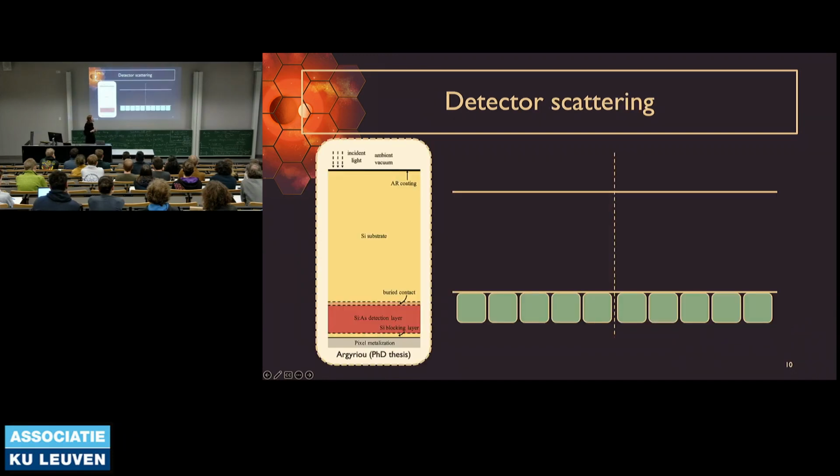So now that we're on the detector, this detector actually has several layers, so you can see here, and each of these layers are actually reflecting at different wavelengths. So due to the efficiency, you're not necessarily detecting your photon at first pass, which means that it gets to scatter around in the detector before it's detected. Because other wavelengths of photons also come in, they kind of interfere with each other. So this results in quite a complex pattern in your spectrum.